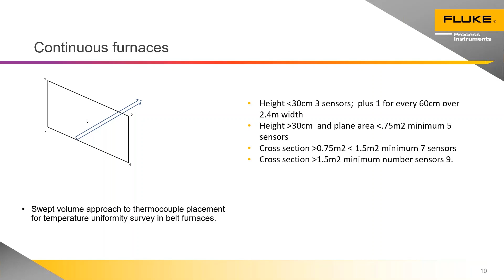So it's quite a complex thing to build the frame to pass through the continuous furnace. The frame obviously has to have feet. It's going to stand upright as it's going through. Also, the sensors have to be within 3 inches of the edge of the working volume, so there needs to be care taken when placing the frame on the belt that it's actually centrally located. And photographs of the frame as it's going into the furnace will always be useful and can be incorporated in the report so that when you come to audit, you can show that you were correctly placed and measuring the working volume.